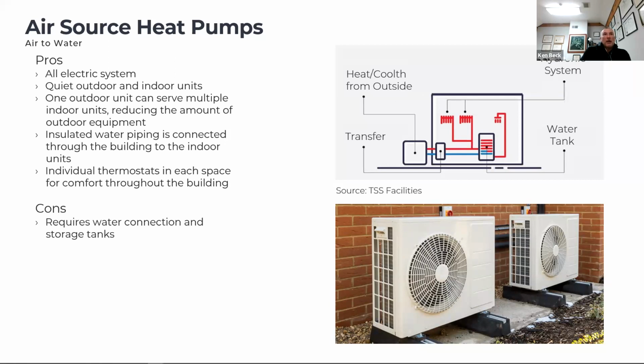And depending on how you pipe the system, you can do simultaneous heating and cooling. It just takes a little more piping to do that. Each space would have its own thermostat for its comfort control. This option would have water running to the outdoors through the air to water heat pumps. So there would be some type of either heat trace on that or glycol in the system. And depending on the volume of the system, you might need storage tanks to have enough water volume in the system so it doesn't short cycle.